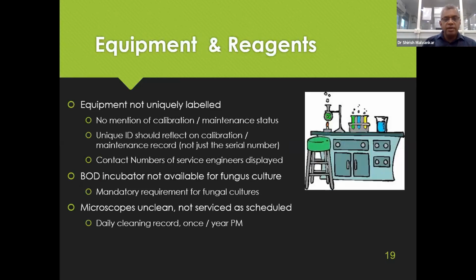Moving on to equipment and reagents. Another common NC is equipment not uniquely labeled. Every instrument, not just in microbiology, but all the equipment in the laboratory needs to be uniquely labeled. There has to be mention of the calibration or the preventive maintenance status of the instrument on the label itself. What are the next due dates of calibration or maintenance? This unique ID should also reflect on the calibration and maintenance record and not just the serial number.